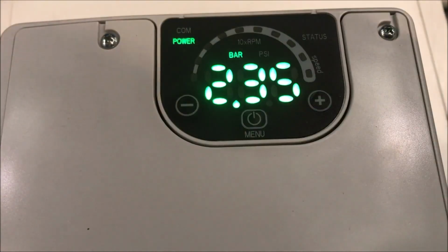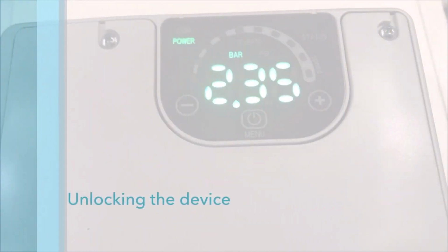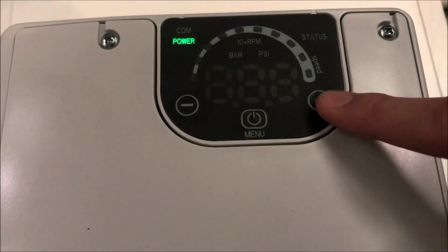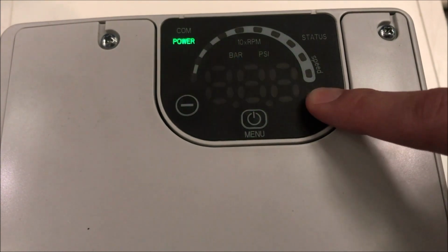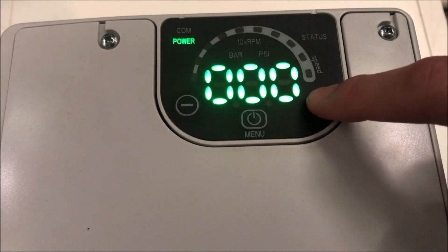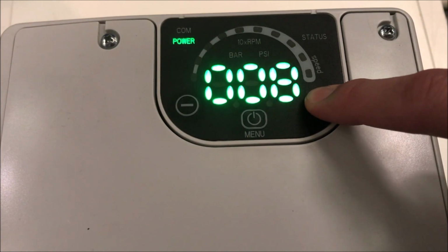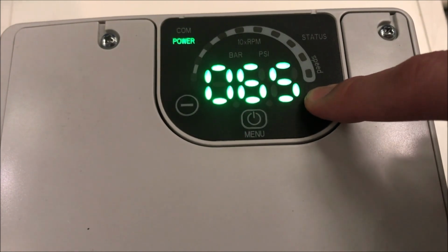To unlock the device, allowing changes to the unit parameters, hold the middle button down for 3 seconds. You will then be taken to parameter 20. Press the middle button to confirm. Then use the increase and decrease buttons to enter the code 065.